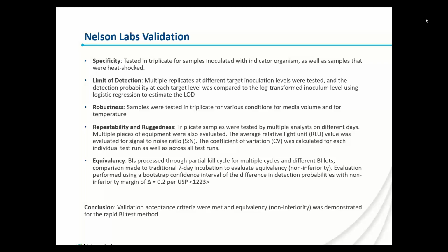For robustness, the samples were tested in triplicate for various conditions, for media volume and for temperature. The reason for approaching robustness this way is to demonstrate that the test method is unaffected by small but deliberate changes that might happen in the course of the test. So that's what we're establishing with robustness. We also tested for repeatability and ruggedness. For this, we used triplicate samples tested by multiple analysts on different days. We also evaluated multiple pieces of equipment. And in this test, we evaluated the average relative light unit, or RLU. This is the way that the system detects the presence of organisms. We evaluated that and compared it to a signal to noise ratio. We also evaluated the coefficient of variation.